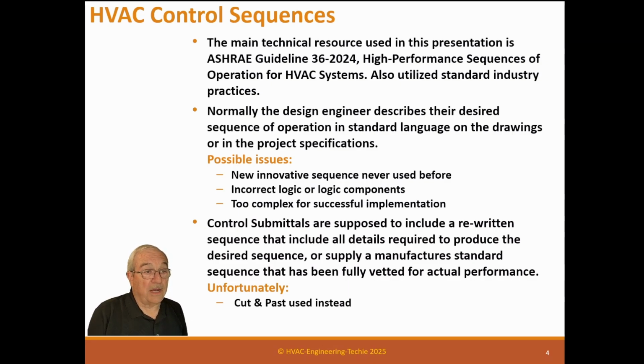Now, the control programmer and I also know that's not what he's going to do. He's going to have to add a bunch of stuff into that. And if you don't expose that, then you won't know exactly what he's doing, and you may not know how to test it, or you won't be able to identify if a test passes or fails. So what happens when we have that kind of situation, where I know they've cut and pasted it, and they do that not to save time, they do that so they won't get disapproved. If they change that sequence to what they're actually going to write, the engineer may just say their submittal's not good, it's not doing my sequence. But the truth is, what we'd really like to have them do is to have a standard sequence, or a sequence that's been written by the manufacturer and fully vetted and tested over many projects. That's the sequence I'd like to use because I know it's a good sequence.